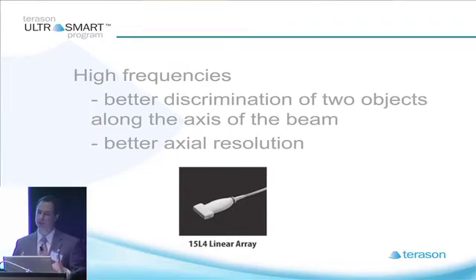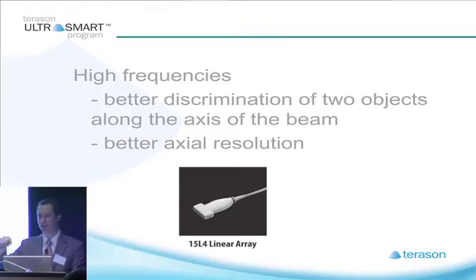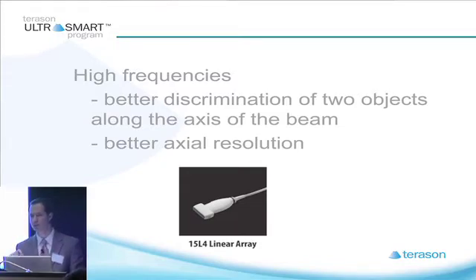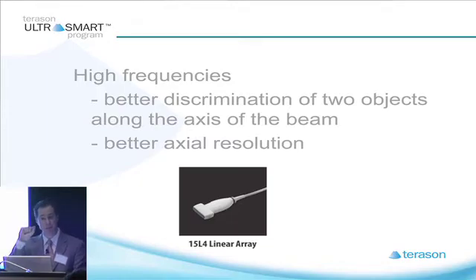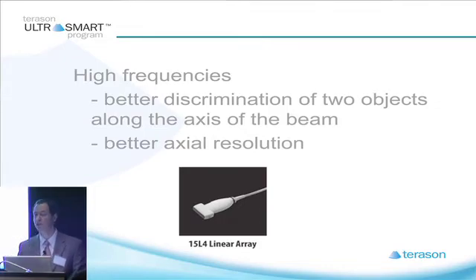Your linear arrays are going to be your higher frequencies. Higher frequencies attenuate more, so they don't penetrate through deep tissue very well and don't penetrate through things that are very dense. But they're very good at discriminating between two objects along the axis of the beam, improving your axial resolution — a type of spatial resolution — which discriminates between two very small structures and is particularly good with superficial structures. Choose your linear array when you need better resolution, but be aware that if you have something particularly deep, you may have an attenuated signal.